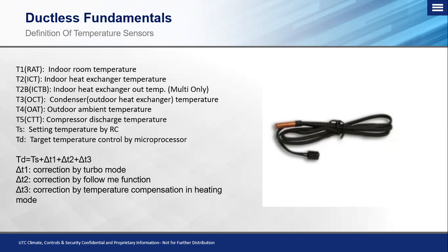Now let's move on to the outdoor unit. The outdoor unit is going to have three main sensors. You're going to have an outdoor coil temperature sensor, an outdoor ambient temperature sensor, and a compressor discharge temperature sensor. Of course, the compressor discharge is protecting the compressor from an overheating situation. The outdoor ambient and the outdoor coil control things such as fan speed and, most importantly, defrost. Okay, but those are going to be the three main sensors that make up our outdoor unit.